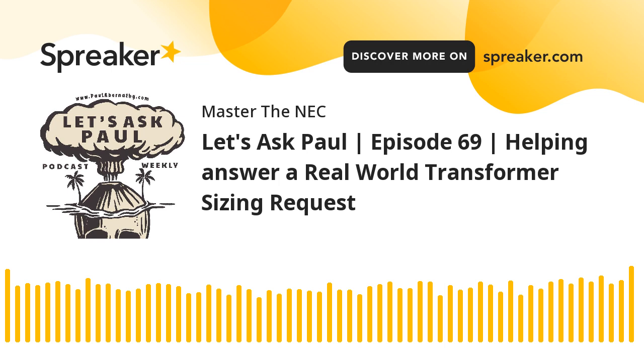Whereas 480, 277 single-phase transformers have a bunch of different ratings, like a 5, a 7.5, a 10, a 15, a 25, a 37.5. You know what I'm saying? So in a three-phase one, 480 volt to a 120/208 Y, and you haven't told me what you're dealing with here, so I'm just leaping a bit, it jumps from 30 to 45.